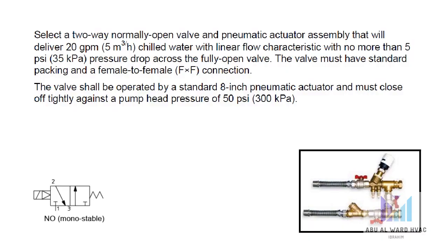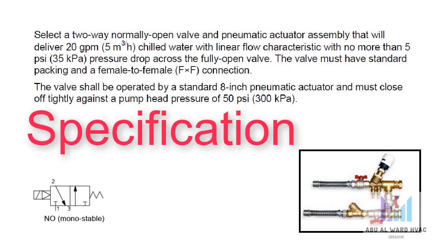Now let's have another example. Select a two-way normally open valve and pneumatic actuator assembly that will deliver 20 GPM of chilled water with a linear flow characteristic, no more than 5 PSI pressure drop across the fully open valve, with standard packing and a female-to-female connection. These are the specifications for what we need to select.